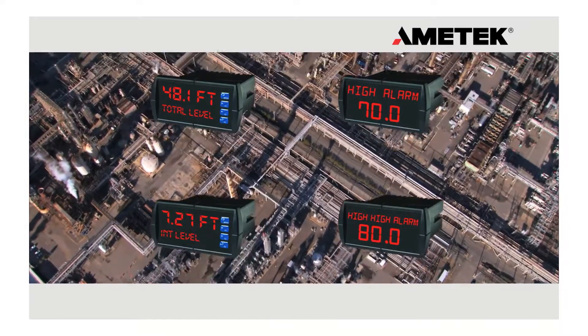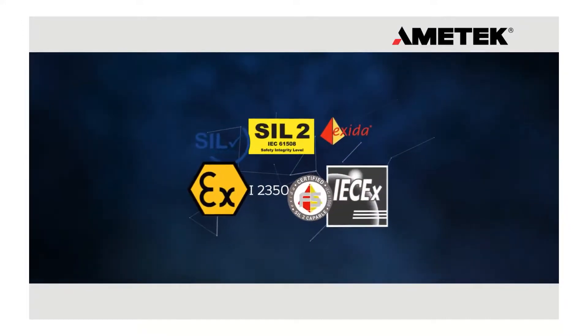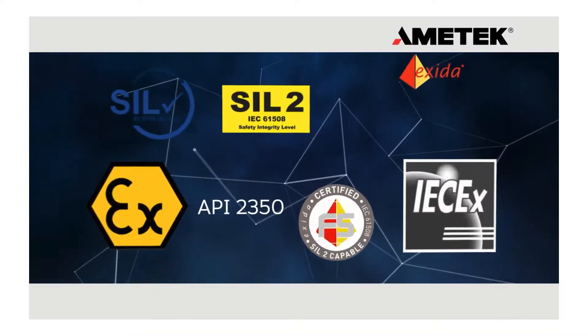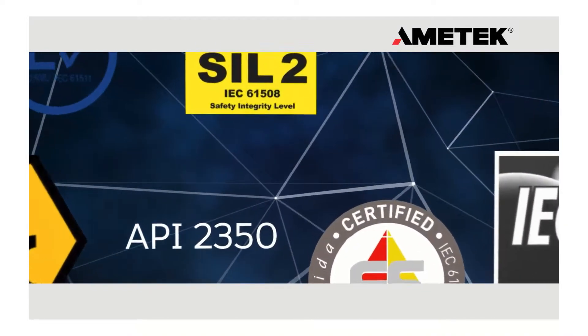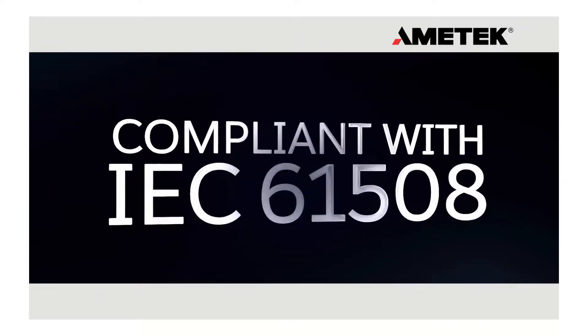Products used in this application are typically required to meet the API 2350 overfill protection standards as well as SIL safety integrity level performance standards to IEC 61508.